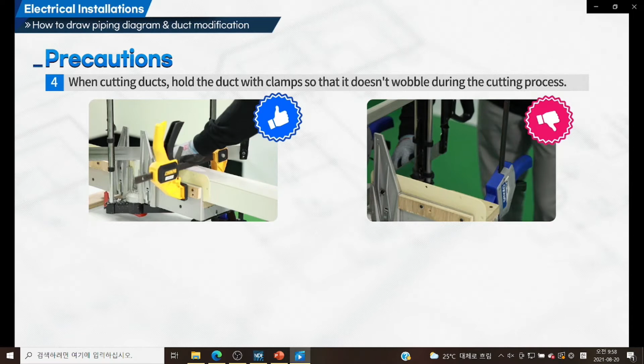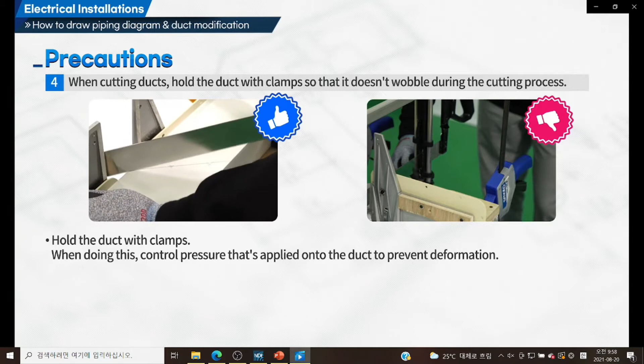Fourth, when cutting ducts, hold the duct with clamps so that it doesn't wobble during the cutting process. When doing this, control the pressure applied onto the duct to prevent deformation. If the clamps hold ducts in the wrong way, the saw might get stuck during the cutting process and the cutting angle cannot be set properly, so make sure the duct is held in the right direction.